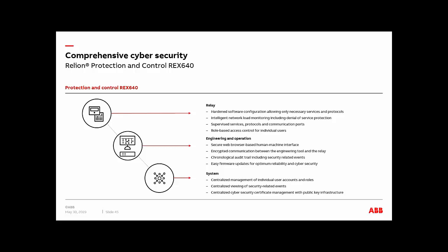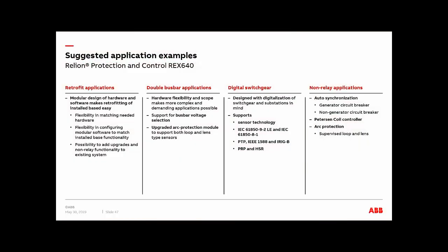We're going to have a secure web browser, encrypted communication between the engineering tool and the relay, which is the PCM 600, and you're going to have your audit trail, as I mentioned before, for all security-related events. So firmware updates are going to be sent to you through ABB when required, and all this will be contributing to making the relay safer when it comes to cybersecurity. So you're going to have, when it comes to the system, centralized management of individual user accounts. You can do this with the PCM 600. You can have a centralized view of security events only, independent of protection, and cybersecurity certificate management with public key infrastructure. So here's some of the suggested application examples.